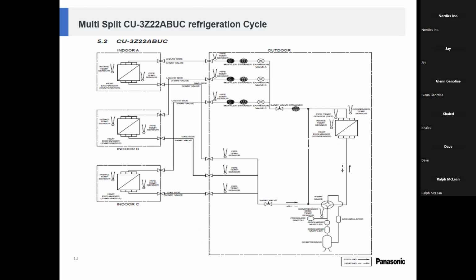Pressure-wise, there is not much difference between R-32 and R-410A. When you're looking at the suction line, our older R-410A was anywhere from 125 to 135. The new one, R-32, is almost the same. In heating, however, it's slightly higher. Slightly higher meaning what? If we were reading 425 PSI with 410A, with your R-32 you might see around 440 to 450, just slightly higher than 410A in heating, not in cooling.